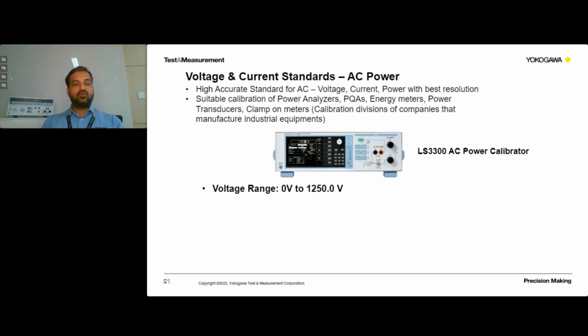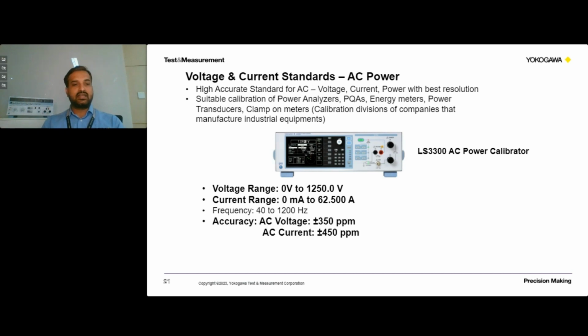And if you can see here, the voltage range is from 0 volts to 1250 volts. So I think this is a decent AC power calibrator with such a wide range of voltage, starting from 0 volts to 1250 volts. When it comes to current range also, if you can see here, from 0 milliamps to 62.5 amps. So what we are indicating with these ranges is that this calibrator has the capability to do the calibration of voltage and current range, along with the power, covering this entire range. So your entire power calibration can be done across the voltage and current range.